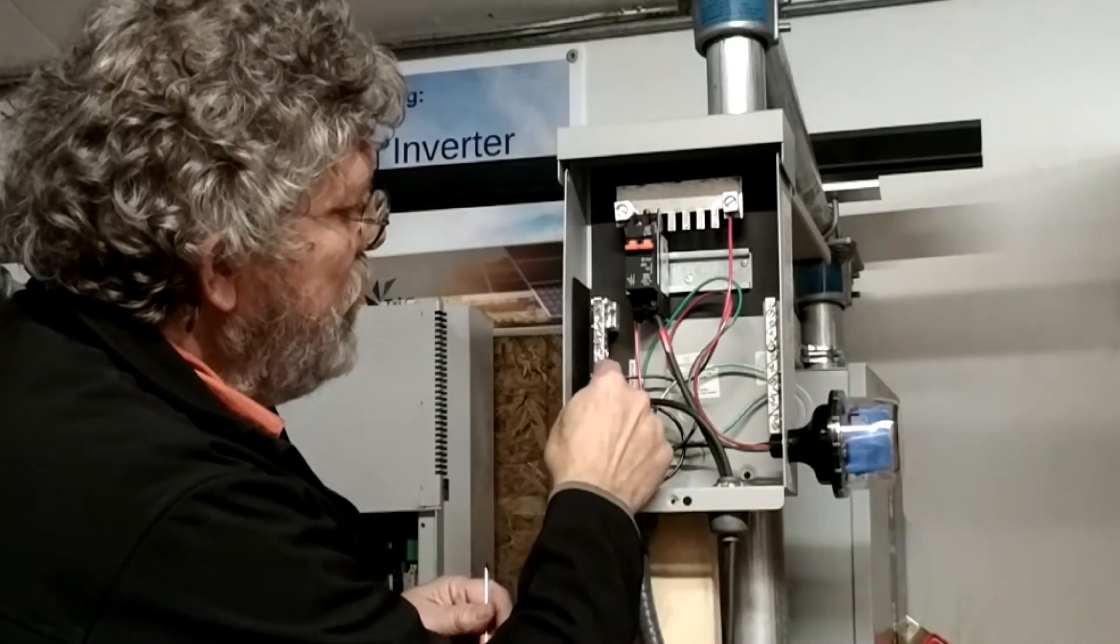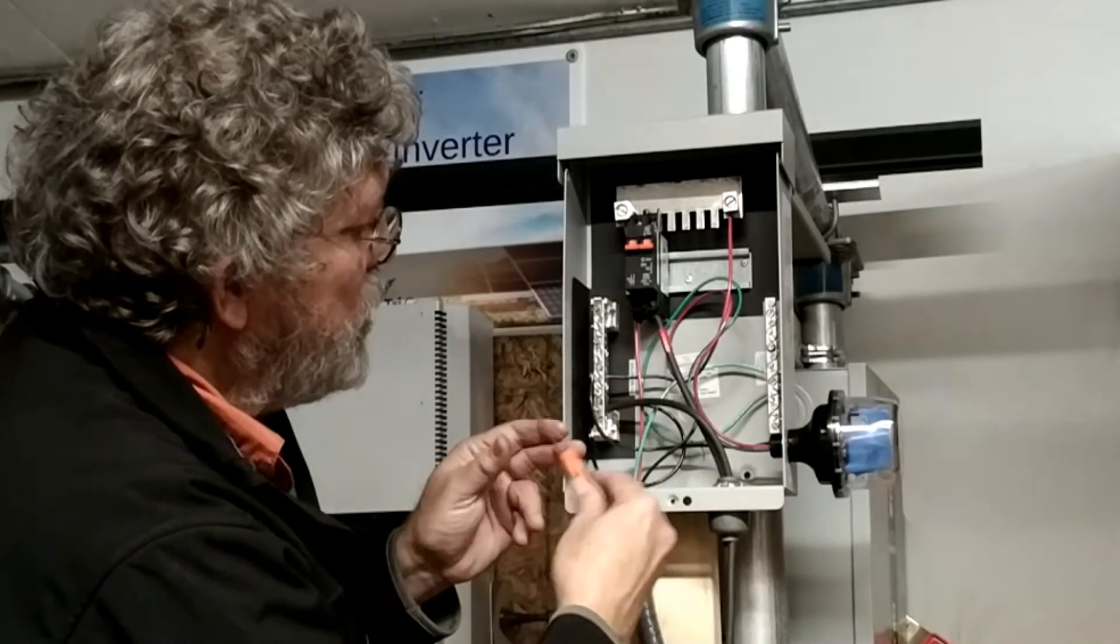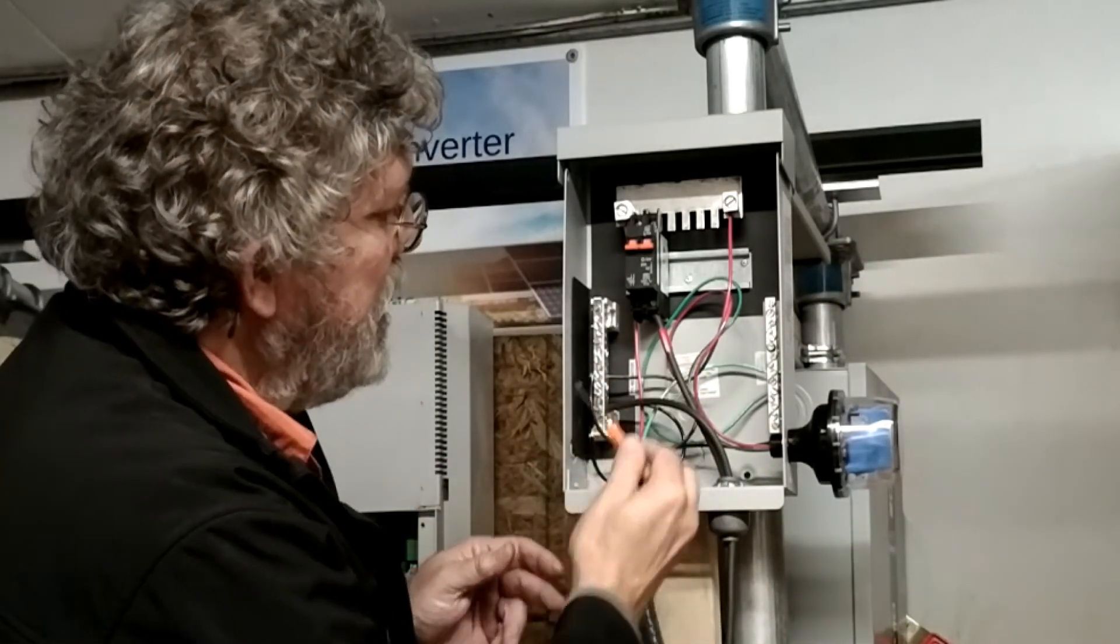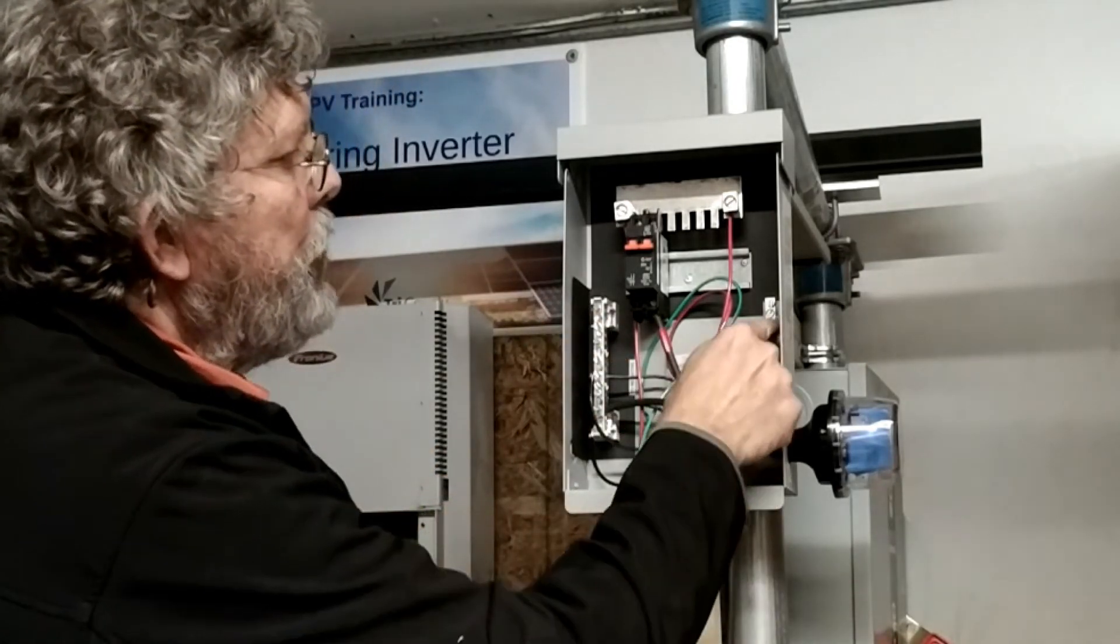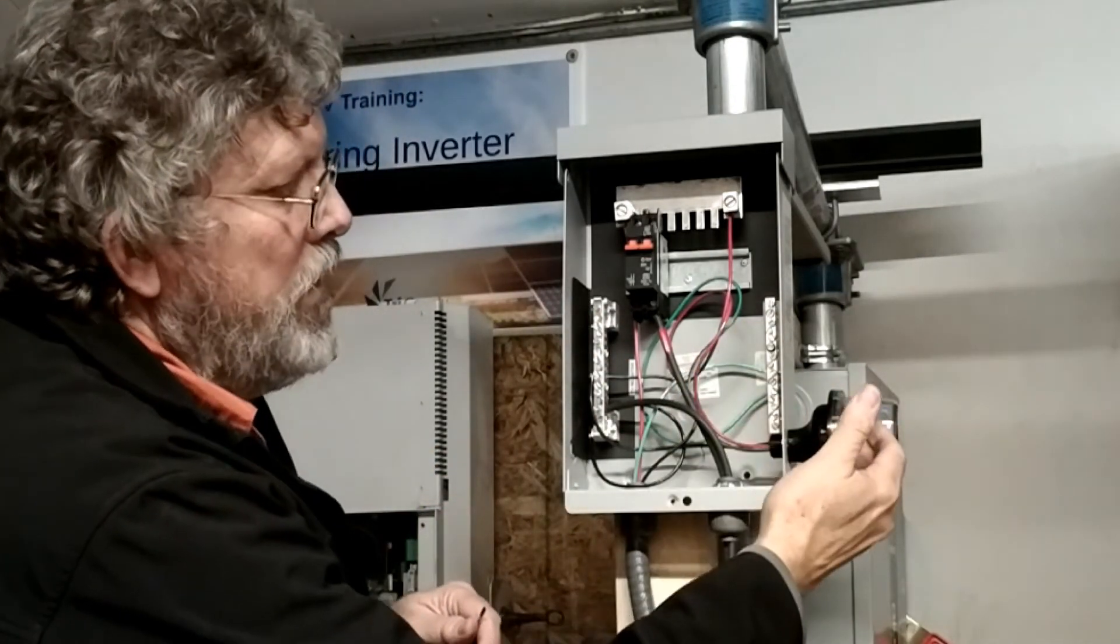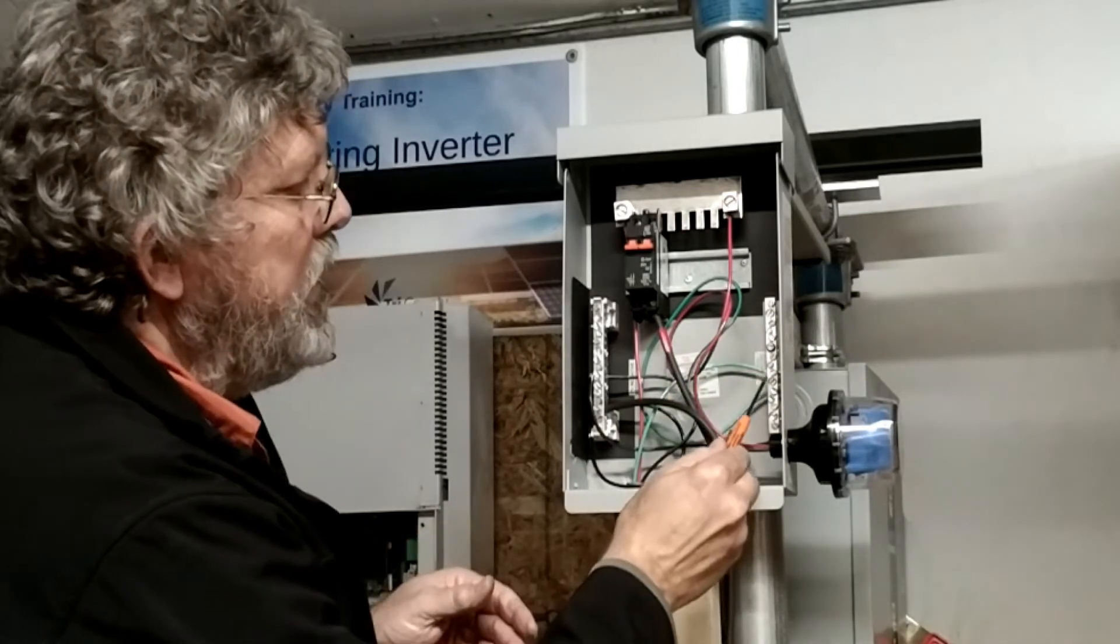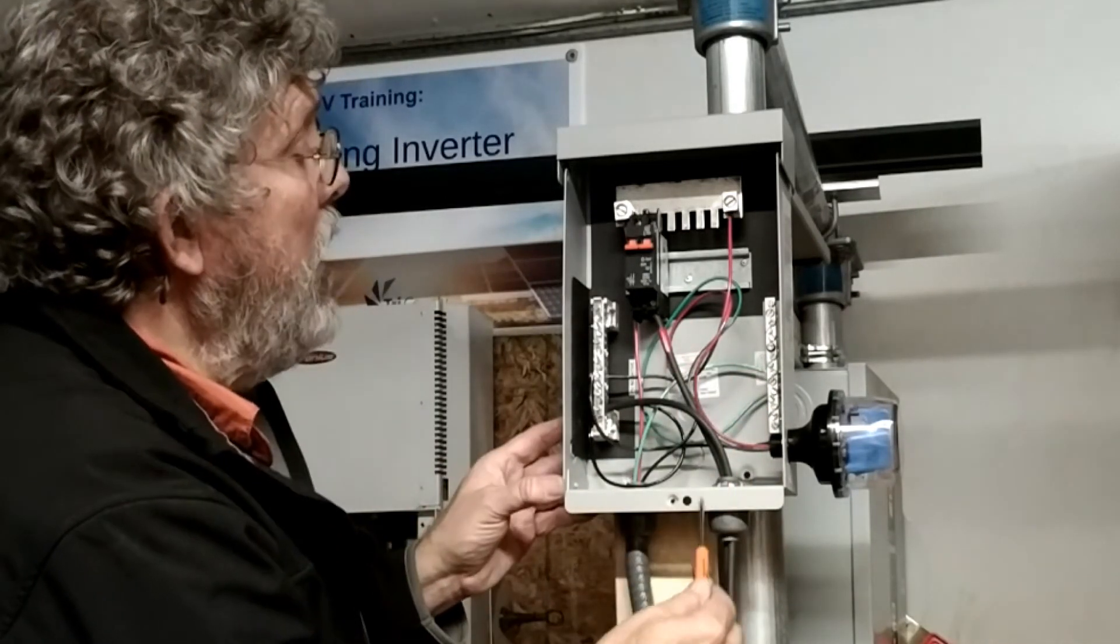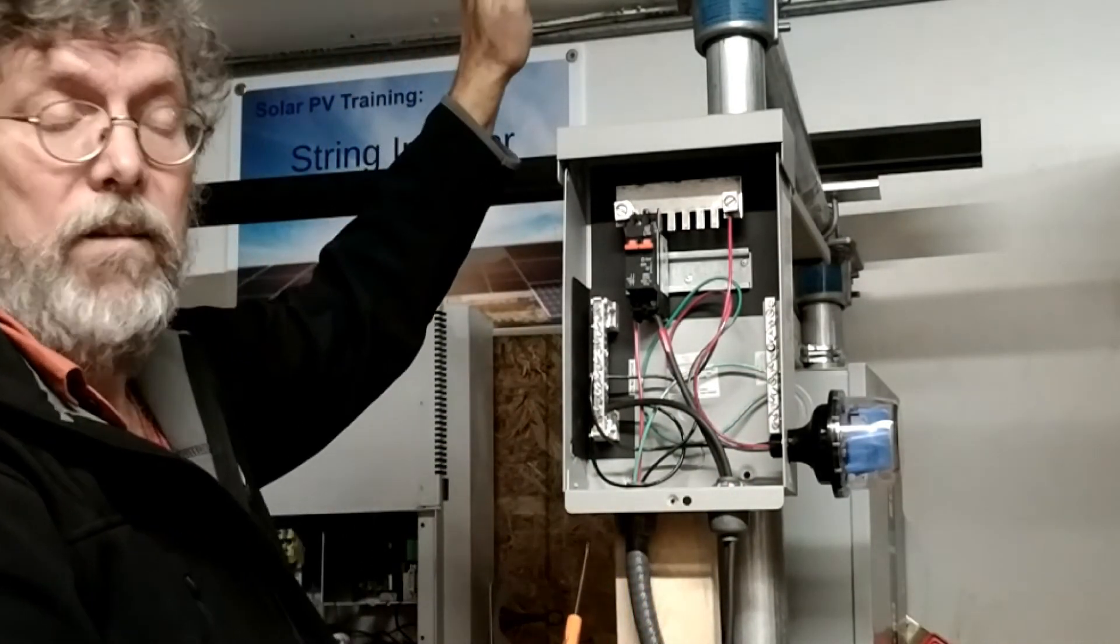The negative wires are all connected in this negative bus bar. So the surge protector negative, the negative from each string would be connected in here into the negative and then the grounding bus bar. The ground from the surge protector gets connected in here and the equipment ground, which is coming in from your PV array, would be connected into here.